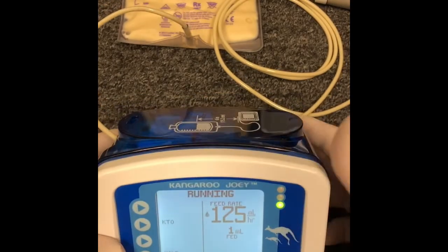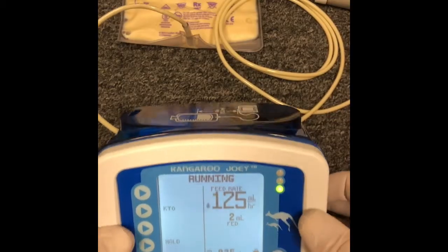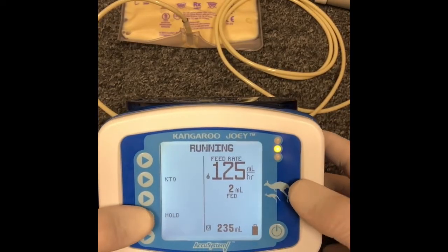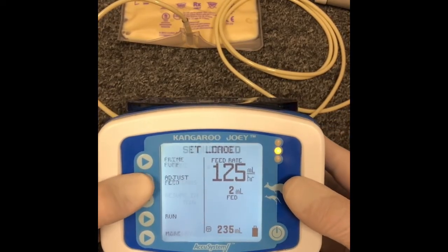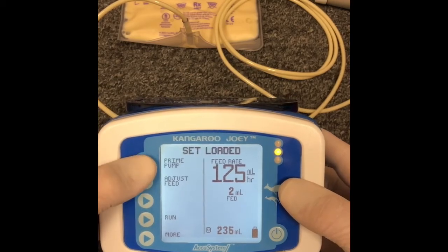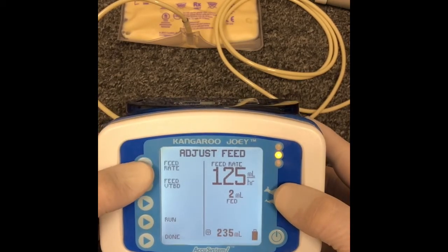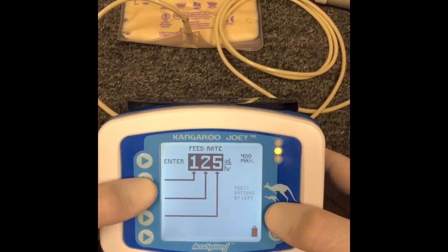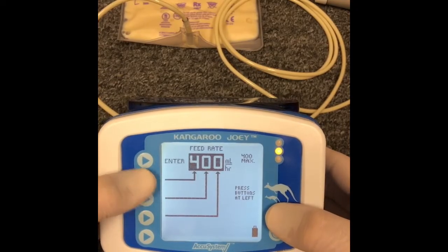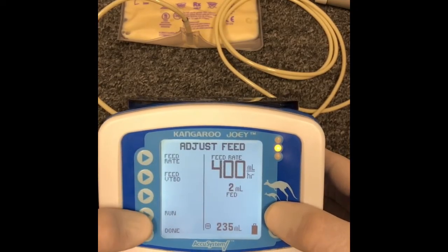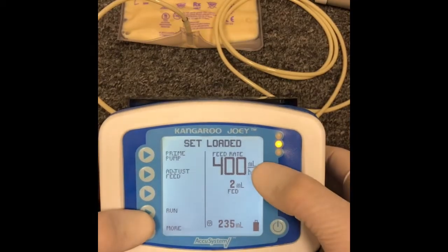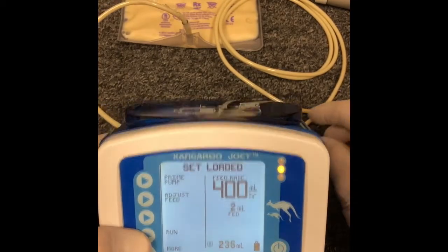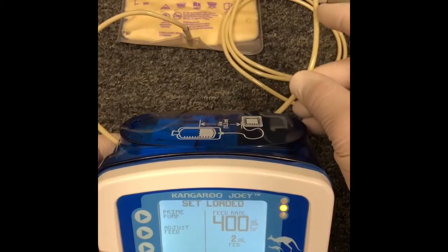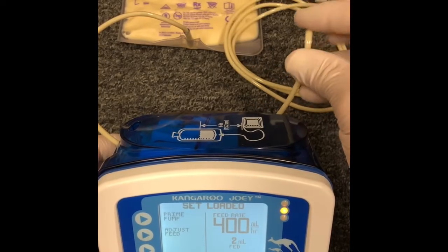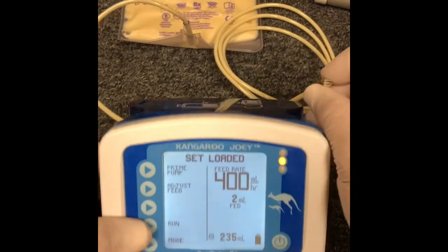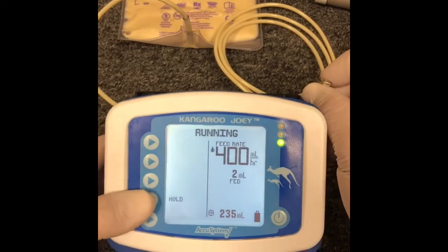All right, we're off and running. And what I want to do is go ahead and pause it really quick, and I'm going to increase the rate so that we can look at an occlusion and see what that looks like. Say there's some blockage down the line. We want to simulate that for you so you can see what that looks like. I've increased my rate to the maximum rate, and I'm also going to pinch the tubing. So let's just say the patient's line is occluded, or the tubing is pinched, and let's see what the pump is going to do.